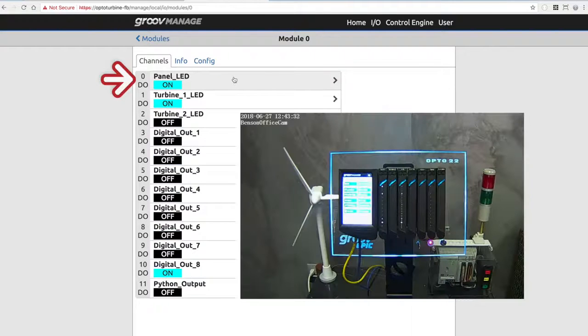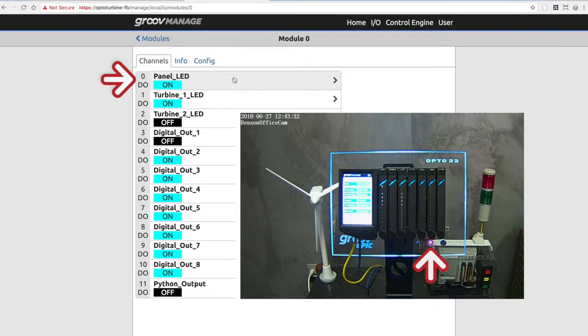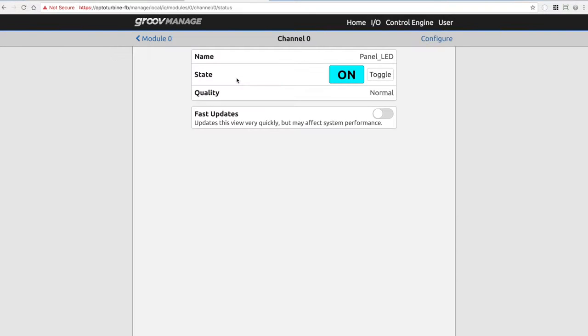In channel 0, I have a digital output. That's my panel LED, a small LED right on the plexiglass panel that I can turn on or off. I'll click on it, and you can see the name of the I/O point, its state, and its quality. I can force the I/O point on or off and check that it's working properly, and indeed it is.